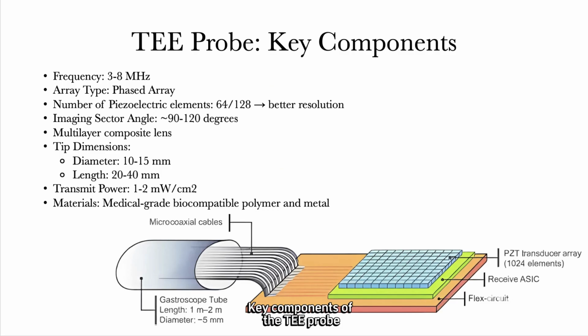Key components of the TEE probe include a 3 to 8 MHz phased array transducer with 64 or 128 piezoelectric elements, yielding high-resolution images within a 90 to 120 degree sector angle. The multilayer composite lens ensures efficient wave transmission. Tip diameter is 10 to 15 millimeters, with a length of 20 to 40 millimeters. Materials used are medical-grade, biocompatible polymer and metal.